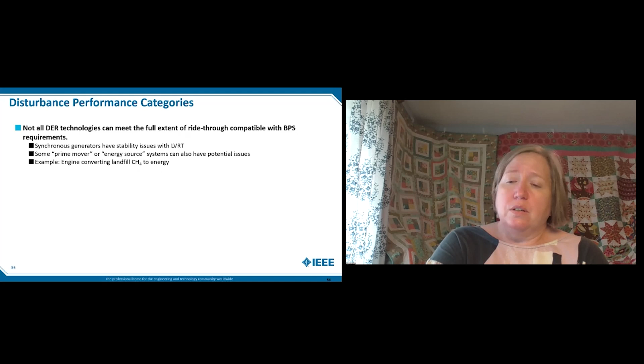Okay, so just as we had on voltage regulation, on ride-through we have performance categories. And this is really because we are technology neutral in 1547, and not all DER can meet the full extent of ride-through that's required to coordinate with the bulk power system. The synchronous generators can't do LVRT. Other rotating machines and energy sources can also have potential issues. So the solution is we have disturbance performance categories.